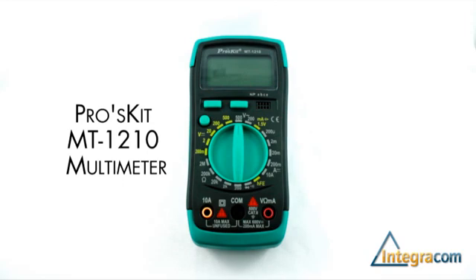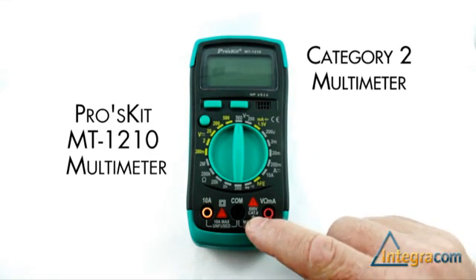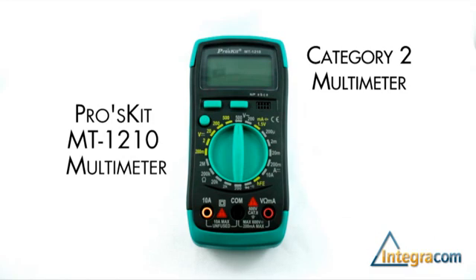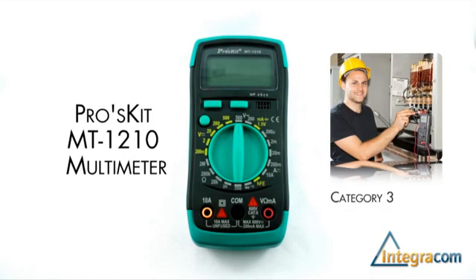All trade quality meters have a category rating. This meter is category 2, which is sufficient for the type of work performed in the telecommunications industry. Electricians might use a category 3 or 4 meter as they use higher voltages.